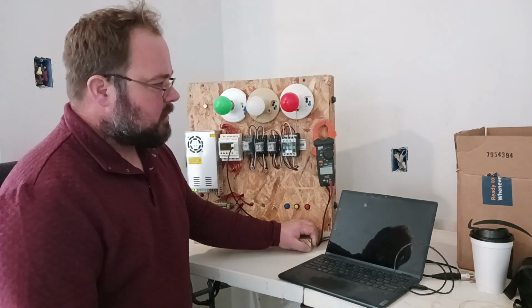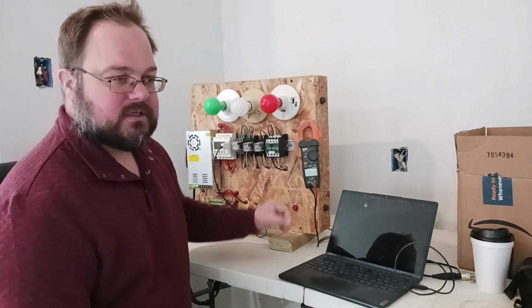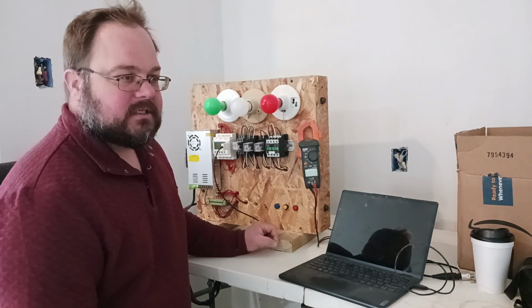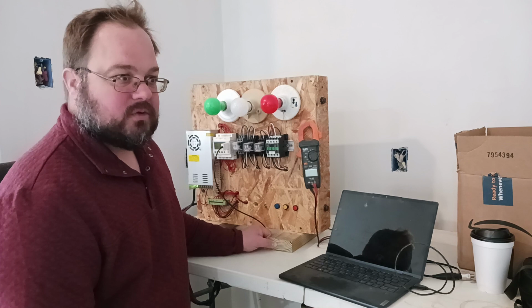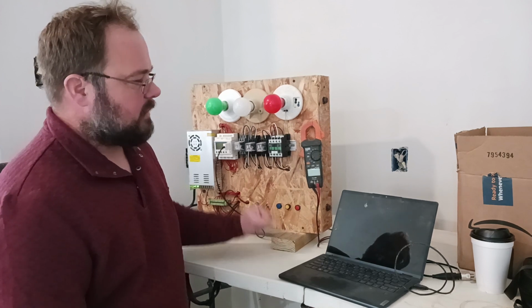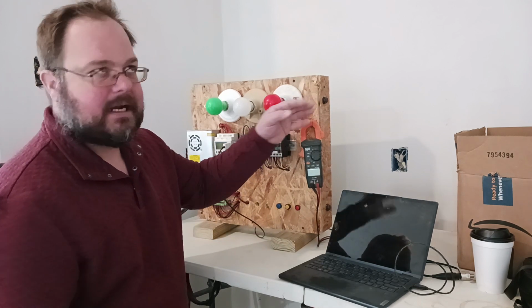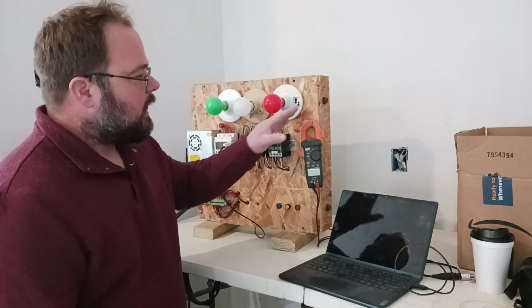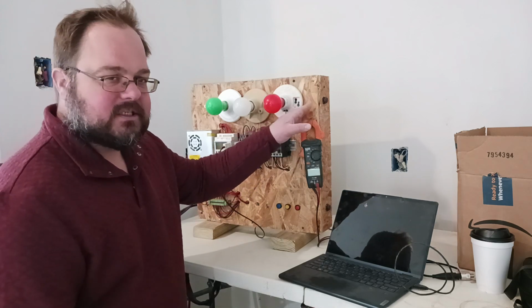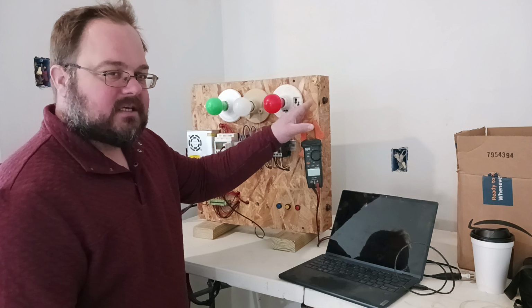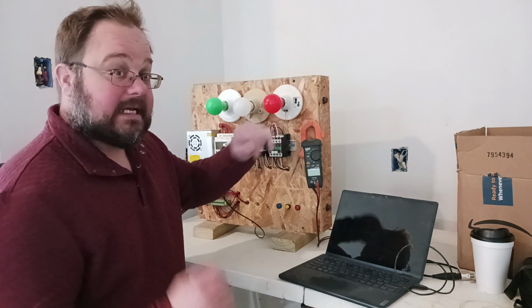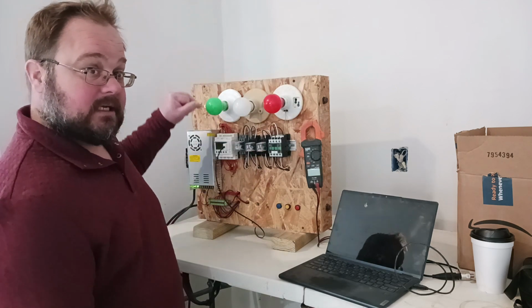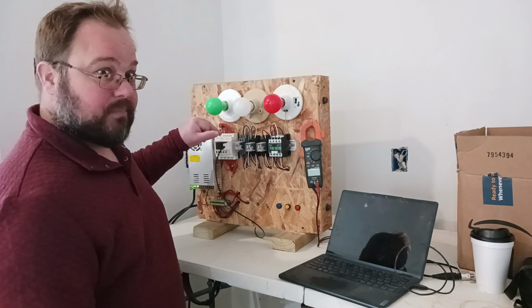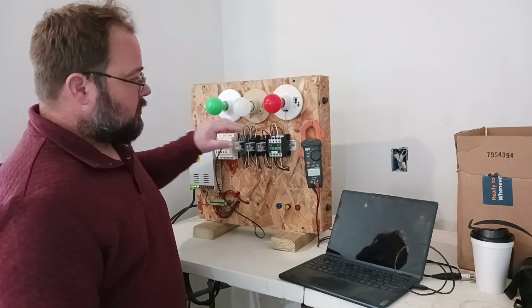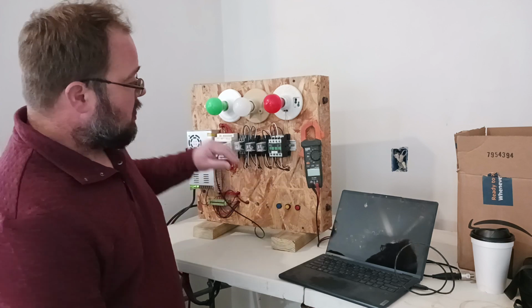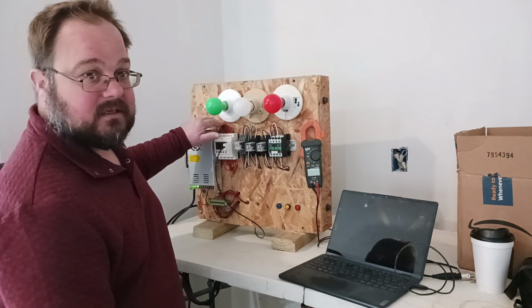Where that really matters is with things like your photo sensors. Some sensors are called sinking or sourcing sensors - for example, these are PNP sensors, and I know I'm throwing out jargon, just bear with me. This PNP sensor needs a positive and a negative to work, and that second P means it's sending the signal as an input as a positive. So, of course, if I have PNP sensors, all my inputs need to be positive.